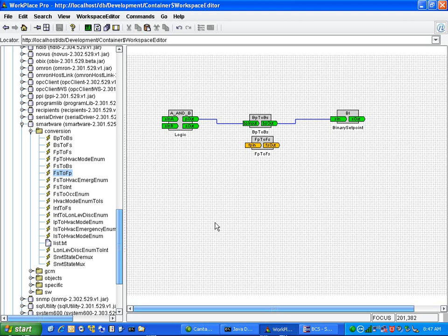What you don't see in here, interestingly enough, is a binary status to binary priority. Why? I don't know. I like them, but if you take a logic block and make it an OR, there's your conversion right there. Your logic OR is typically where you send in a status input and you get a priority output, so you can use a logic OR if you want to convert.